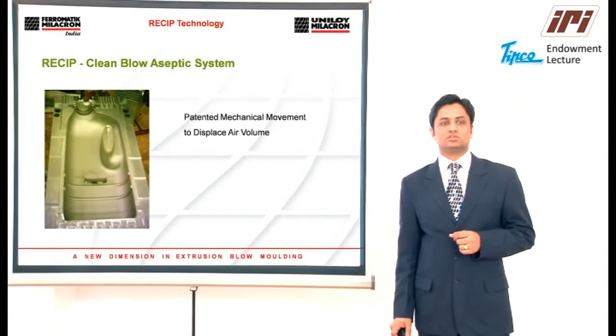The other important part, besides the machine, is the mold for a clean blow aseptic system, because when we blow, hot air is within the container, which needs to be removed back from the container. So mechanical displacement to remove the air volume in the mold is preferred. This is another important feature we look for to get a bacteria-free container.